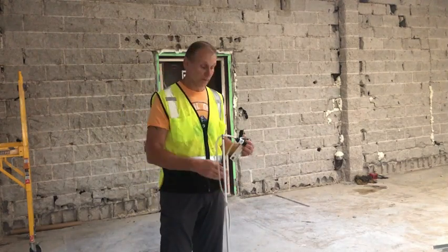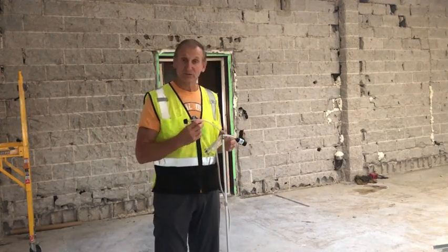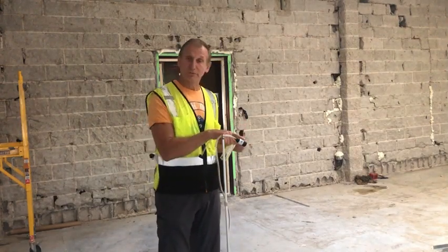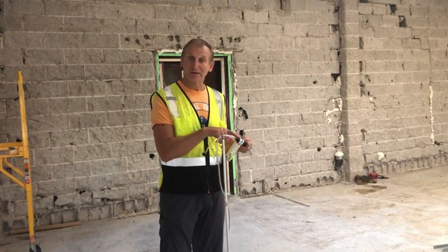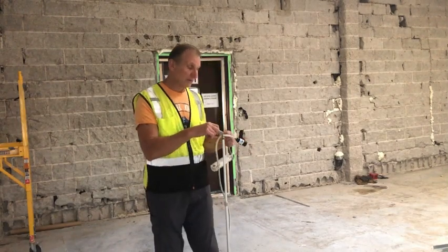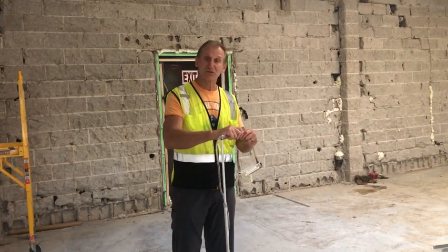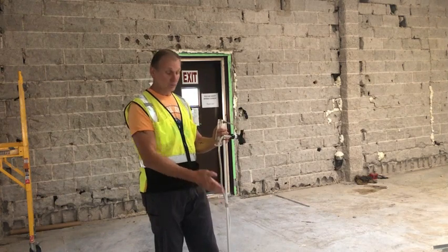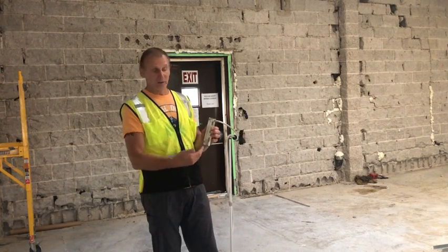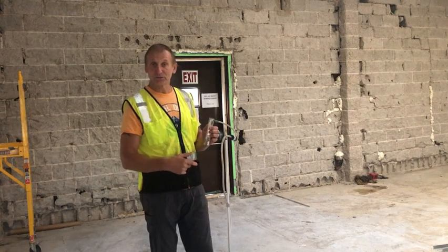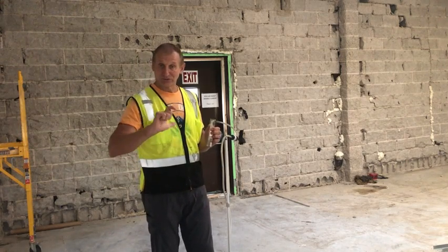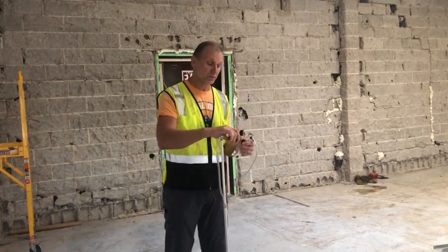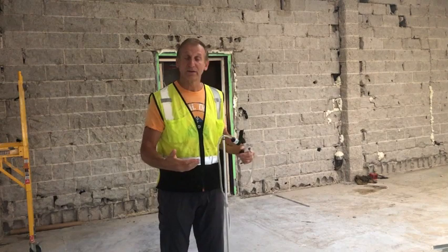Once I put the pump on, I'm going to calibrate it because I want to know the airflow. We have to know the air volume which passes through the cassette so we can quantify the result, right? So, a very simple method again. It's all simplified because this is field work, so most of the time there's no high requirement. Once I put the pump on, I will see the airflow here.